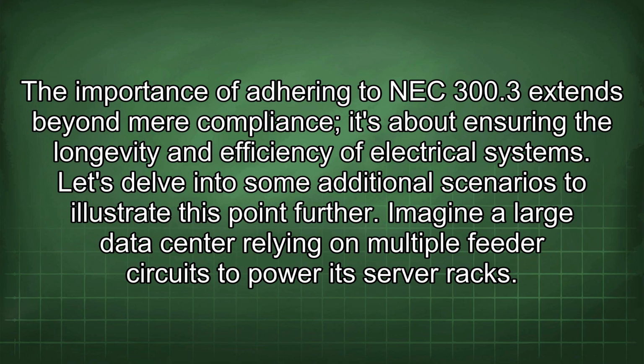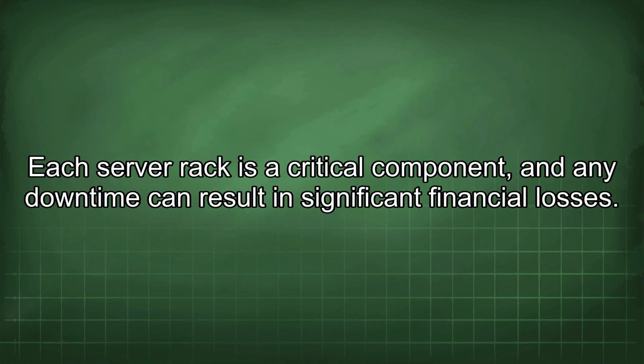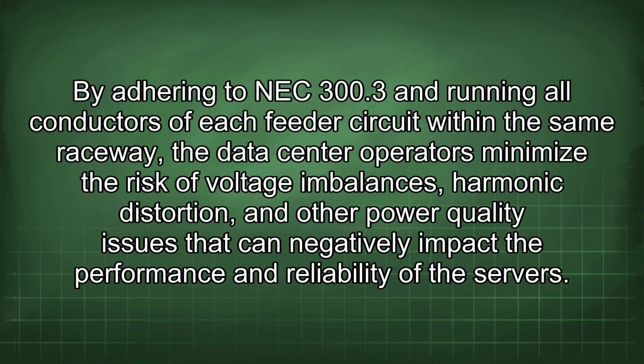Let's delve into some additional scenarios to illustrate this point further. Imagine a large data center relying on multiple feeder circuits to power its server racks. Each server rack is a critical component, and any downtime can result in significant financial losses. By adhering to NEC 300.3 and running all conductors of each feeder circuit within the same raceway, the data center operators minimize the risk of voltage imbalances, harmonic distortion, and other power quality issues that can negatively impact the performance and reliability of the servers.